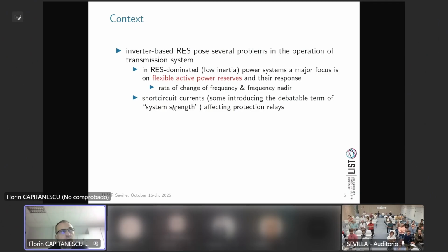Related issue, active power this time again, is short circuit currents. You know that all these power electronics have limited capability to provide short circuit current under fault, and that strongly affects the proper operation of protection relays. We have a little bit less research on that, but there are some people who came up with new things and new terms.